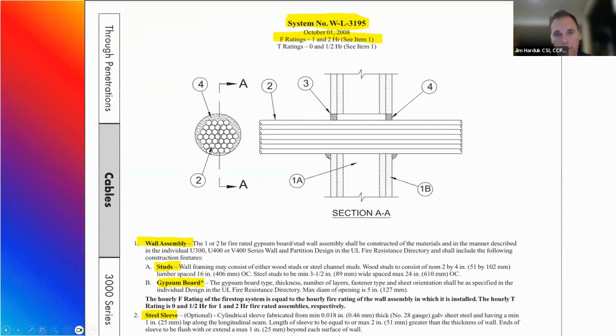And the end result took me to this system drawing. And if you remember back from the UL nomenclature, this particular system begins with a W, which indicates it's a wall assembly. So this is a gypsum wall assembly. And it could be either 1 or 2 hour rating. And again, these are always laid out the same way, where you have the system number at the top of the page. You have the applicable F, T, or W ratings. There'll be a little diagram showing the actual condition. And then, of course, there'll be some text describing what your wall assembly is and some of the other key components of this system. Next slide, please.